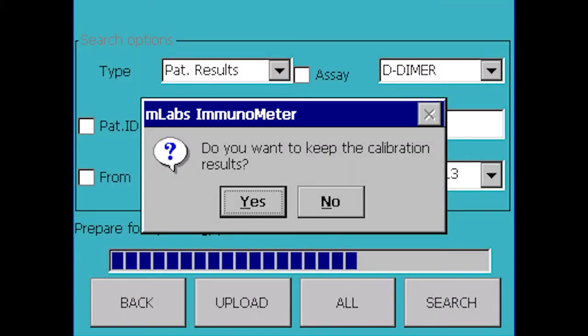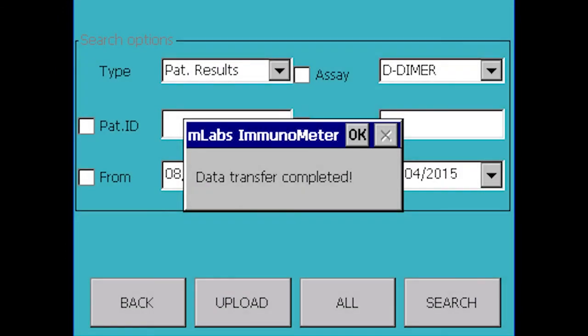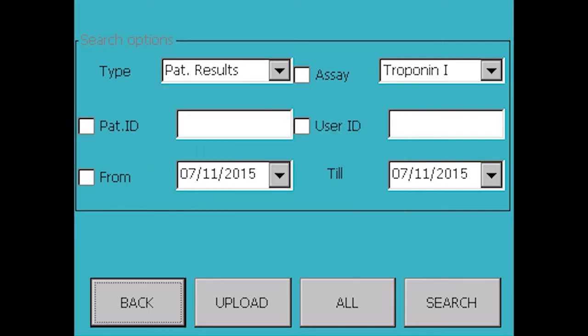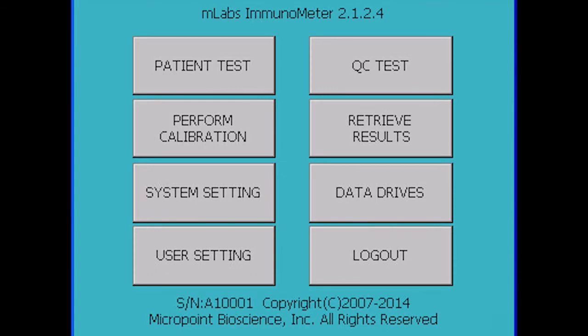A system prompt will ask if you would like to keep calibration results. Tapping Yes will keep the results. Tapping No will remove all the results from the mLabs ImmunoMeter. When the upload is completed, the screen will indicate data transfer completion. Tap OK to close the window before removing the USB drive. Tap Back to return to the main menu.